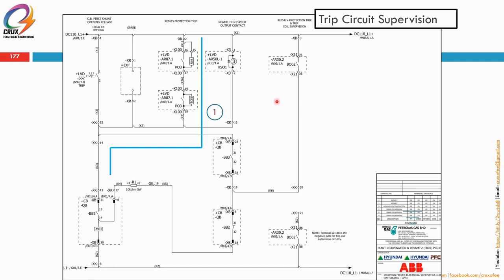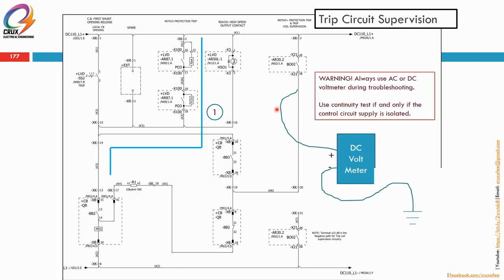So just to add another note, how do we actually check the condition of the supply? Let's say you want to check whether the coil is okay or not. When we want to check something on the control circuit, we always assume that it's alive. So never use continuity or the ohmmeter. Always use an AC or DC voltmeter during troubleshooting. Unless you confirm by checking that there's no more AC or DC voltage on that circuit, only then can you use the continuity test, or the ohmic test. But for me, I always prefer to use an AC or DC voltmeter. That is the safest.